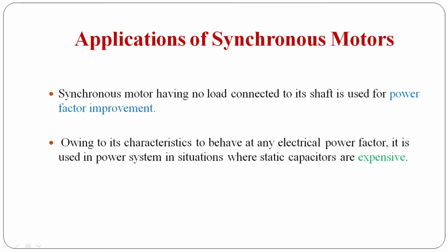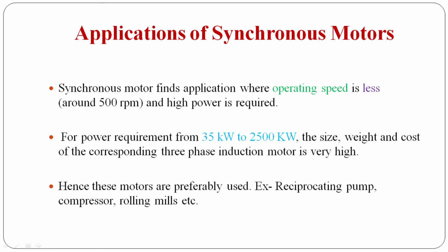A synchronous motor having no load connected to its shaft is used for power factor improvement. Owing to its characteristic of behaving at any electrical power factor, it is used in power systems in situations where static capacitors are expensive. Why are static capacitors used? To improve the power factor. So synchronous motors can be used when static capacitors are expensive, to improve the power factor in various electrical equipment.